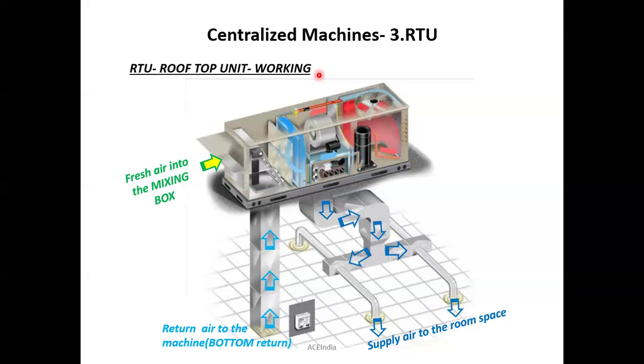That means here you can see two types of ducts. The first one is the supply air duct and the other one is the return air duct. The purpose of the supply air duct is to deliver the cold air to the room, and the purpose of the return air duct is to deliver the hot and humid air to the mixing box. So that's how the return air and fresh air mix right inside this area, and it is again sent back to the supply duct itself. So this is how the cycle goes. Normally, RTUs are preferred for something like 3-story, 4-story, or 5-story buildings. That's how it works generally.